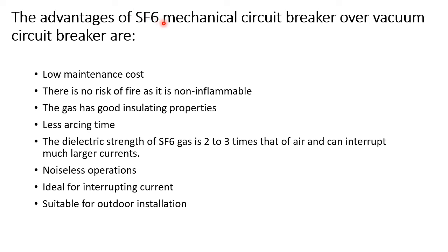The advantages of SF6 gas circuit breaker over the vacuum circuit breaker. So it has low maintenance cost, no risk of fire as it is non-inflammable. The gas has good insulating properties, less arcing time. The strength of the gas is 2 to 3 times that of air, so it can interrupt much larger current. Noiseless operation, it is ideal for interrupting current, suitable for outdoor installation.